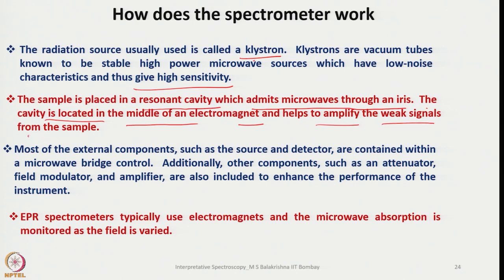The radiation source usually used is called a klystron. Klystrons are vacuum tubes known to be stable, high power microwave sources with low noise characteristics that give high sensitivity. The sample is placed in a resonant cavity between the magnets, which admits microwaves through an iris. The cavity is located in the middle of the electromagnet and helps to amplify the weak magnetic signals from the sample.